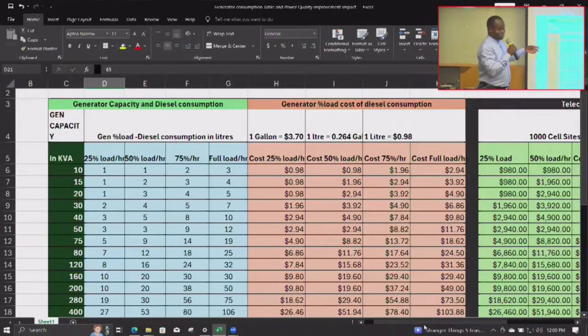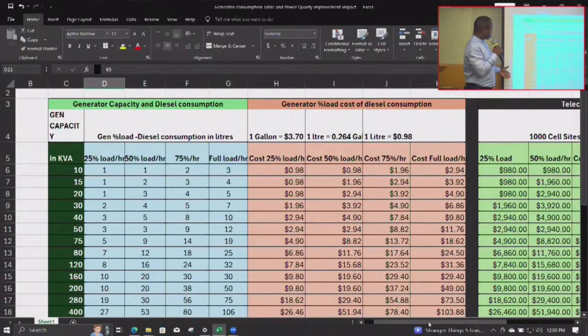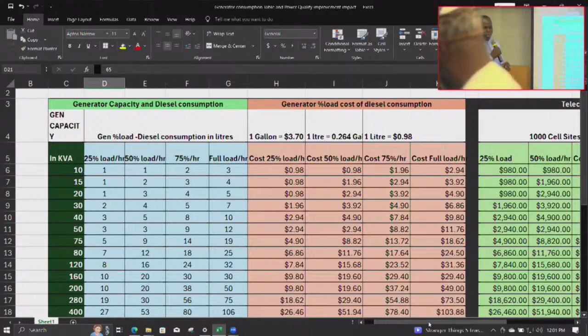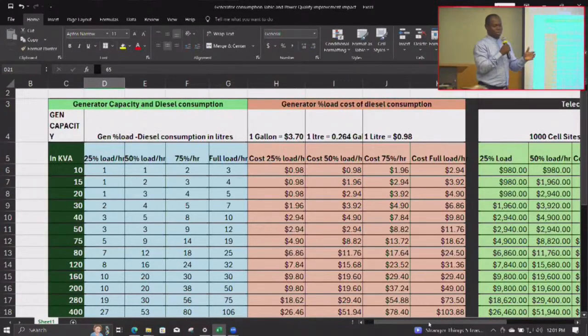If it's not real life, I have somebody from Mantrack here who will tell us we're wrong. So we set up generator percentage load against diesel consumption in liters, with generator capacity in kVAs. We looked at 25% load per hour, 50% load per hour, up to 75% load per hour, and full load—if there's anything like full load, that's above 75%. The generator doesn't really have a lot of space beyond that.